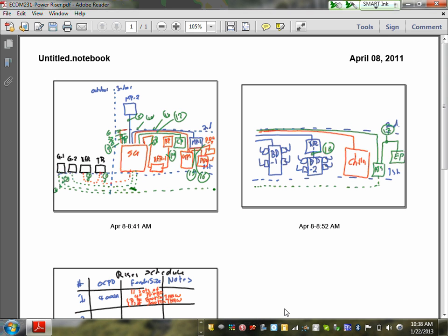So, well, this one, we had three utilities and 12 gens. So we had a utility, gen, utility, gen, utility, gen. And all those neutrals were hooked up and all of them were feeding down to the lowest. Well, we had so many redundant neutral paths that the ground fault system was puking on itself. So we had to put in a whole bunch of four-pole breakers to start switching the neutrals back and forth. So yeah, we do make four-pole breakers.